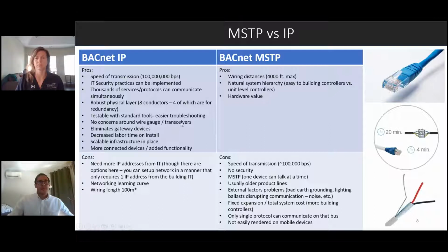And that comes down to it being consistent with your wiring gauge and transceivers at the controllers - it's the exact same RJ45 clip going in. So you can now start to leverage things like patch cables - you could go to Radio Shack, Best Buy, any of these places and pick up a 25-foot patch cable to go from one controller to the next, rather than having to put on clips in the field. You can just get a prefabricated cable, which saves time and effort on the installation side. This little diagram even points out the much faster termination speeds when using IP communication.